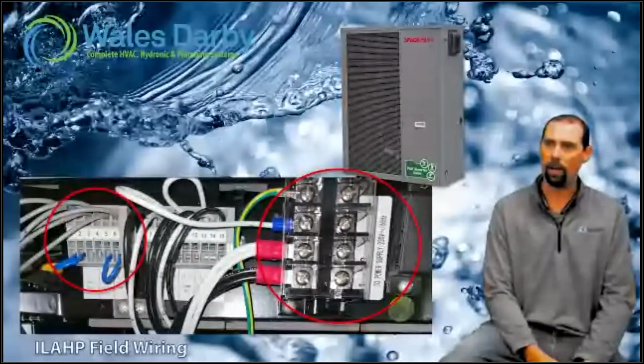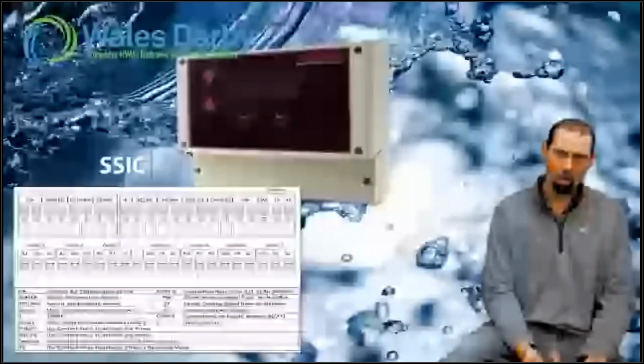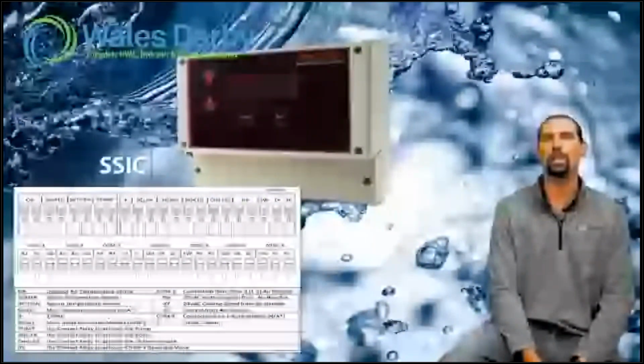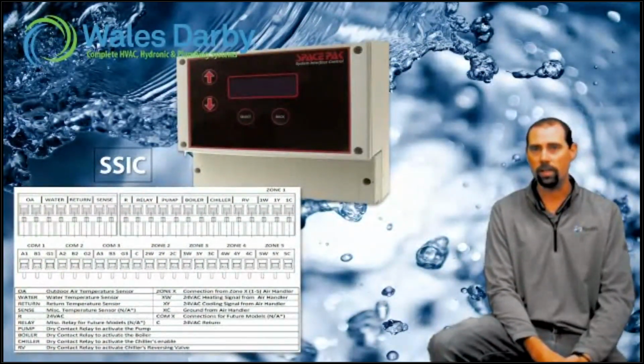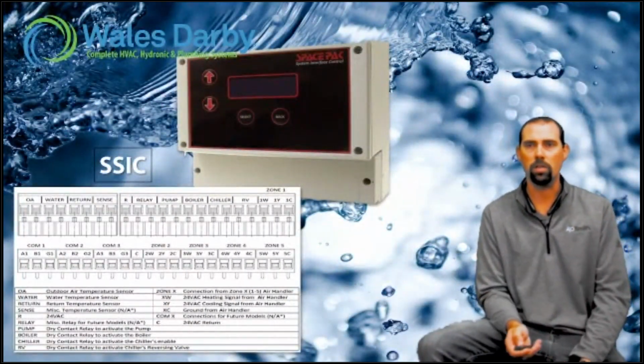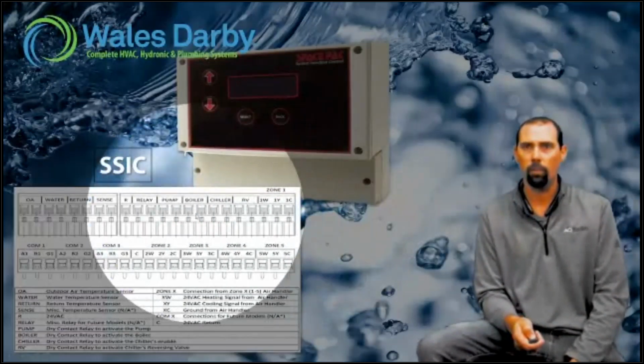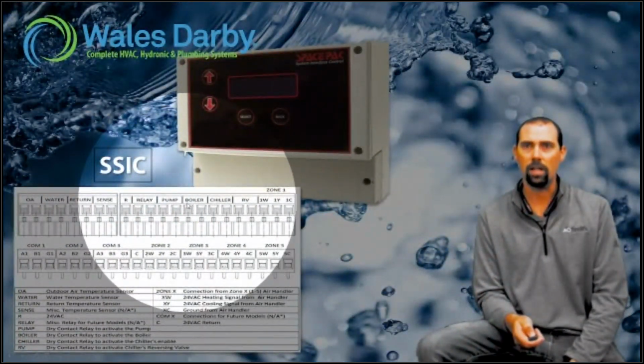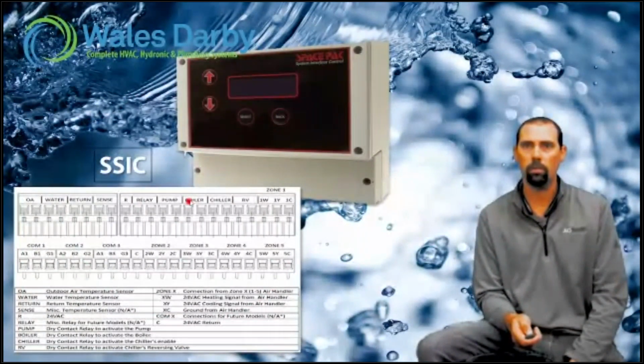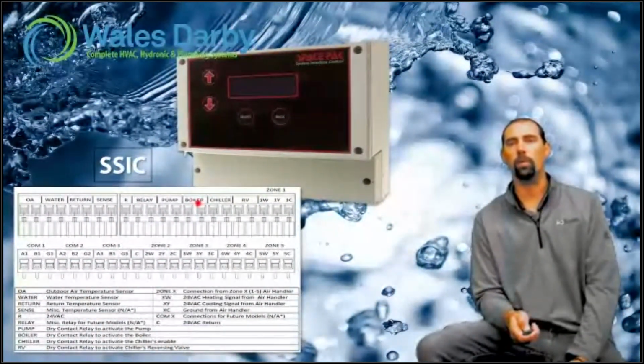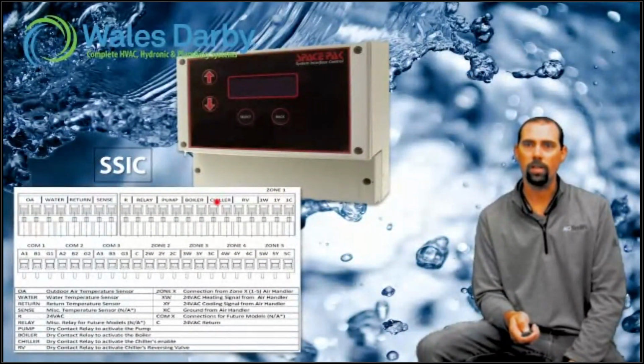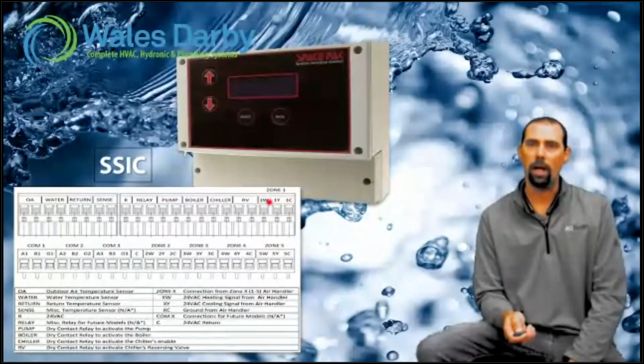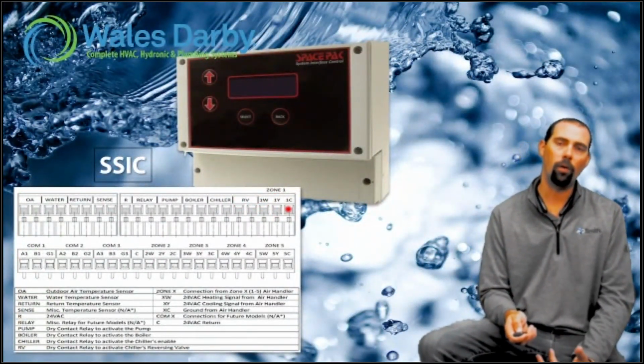We do have some nice schematics, which we'll take a peek at, but we do all of that with this SSIC control. This is a SpacePack interface control. This makes things so easy when we talk about understanding what's calling, getting to the boiler side of things, and we'll look at that diagram coming up more in depth. We got the boiler contacts here. We're doing a backup. We got our outdoor unit, so this is our on-off, our reversing valve, so that's our heating, cooling. And then you'll see we have up to 5 zones, and that's gonna be our input signals.